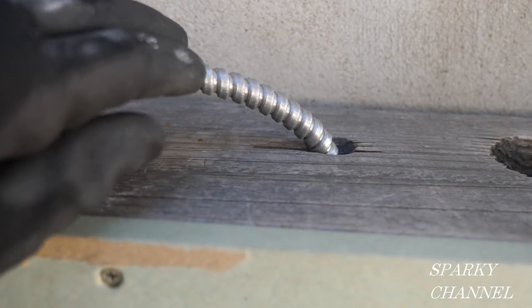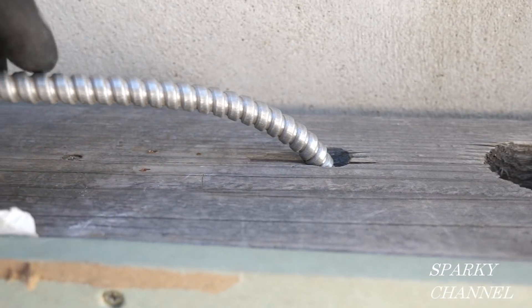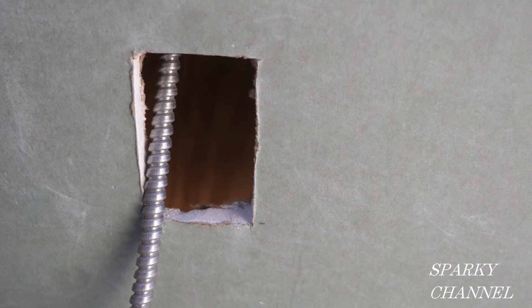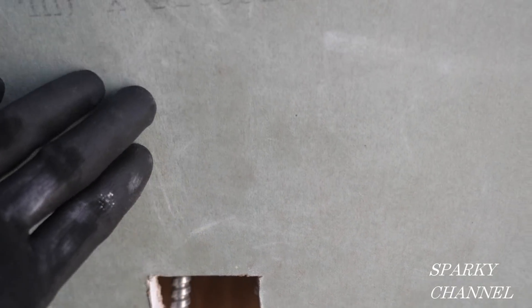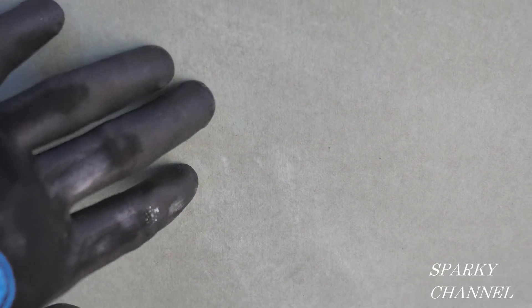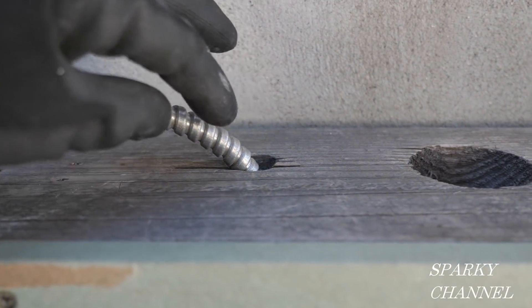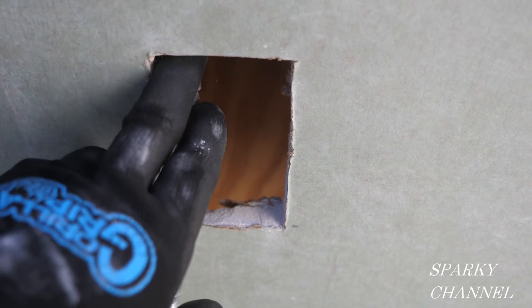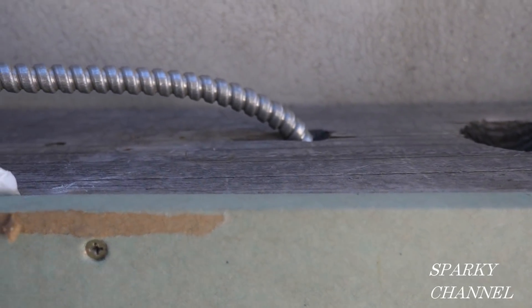Hey, this is Bill for Sparky Channel. Let's say you've crawled up into an attic and you've drilled a hole right here, and you have fished some MC cable behind a nicely finished wall. You go down about seven feet or so — maybe you're putting in a receptacle — and what I want to know is: do you think this is legal by the 2020 NEC code? Can you fish this MC cable behind a finished wall without supporting it while it's behind the wall? Now, up here, if you can get up there to drill this hole, I'm sure you can put a staple right here to support it, and of course when you put in your receptacle it will be supported at the box — but behind the wall, no support.